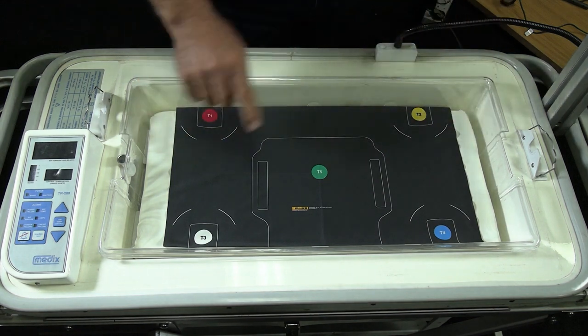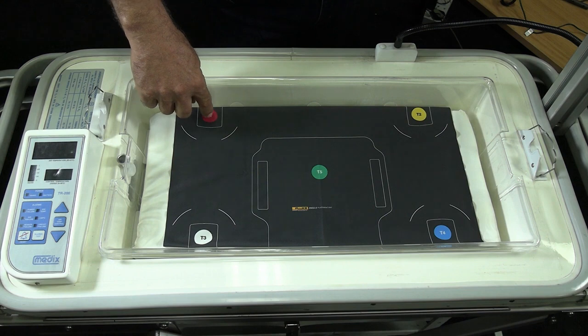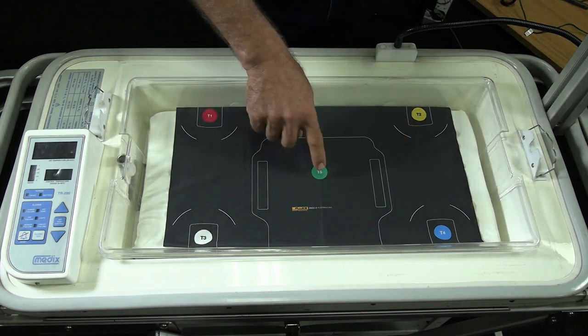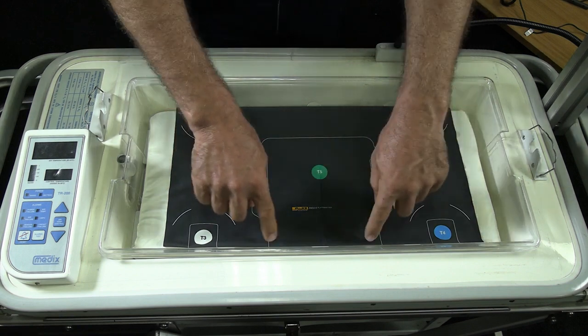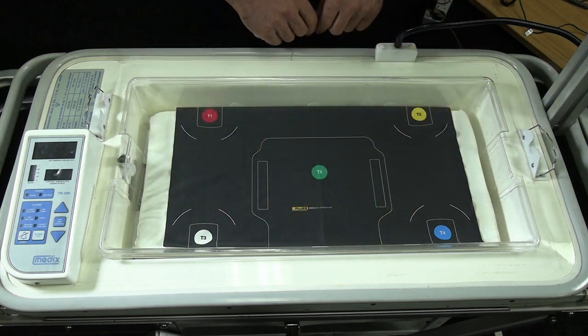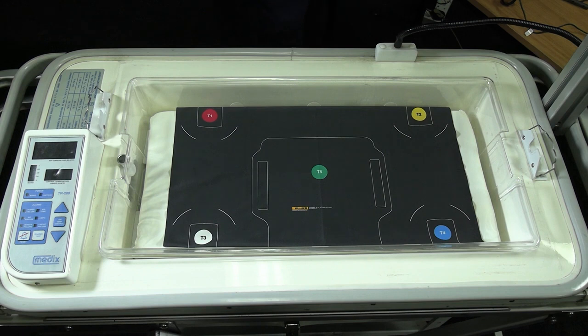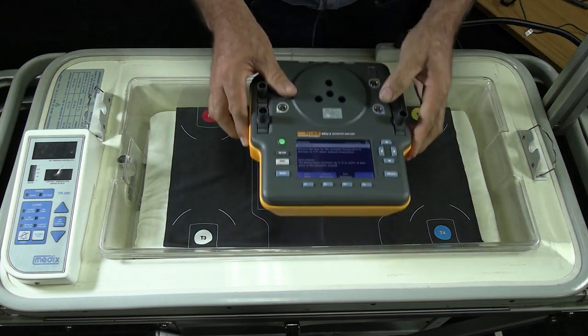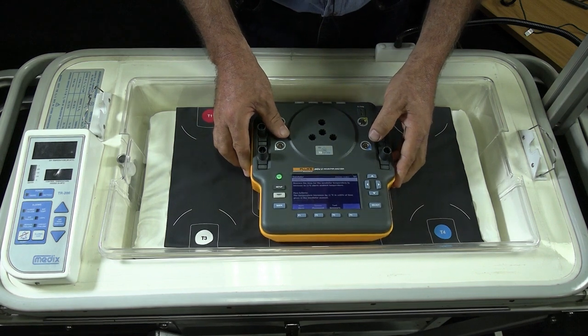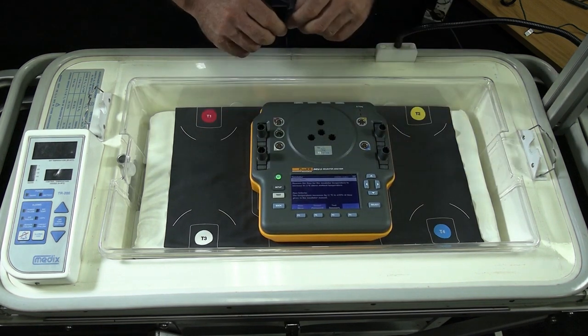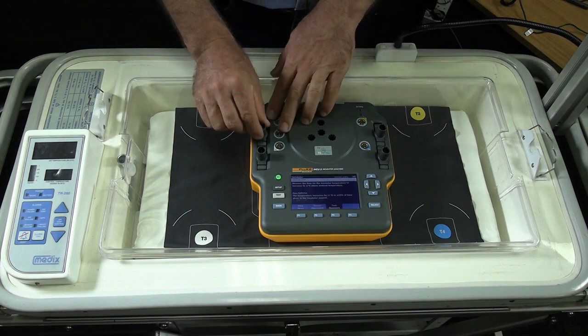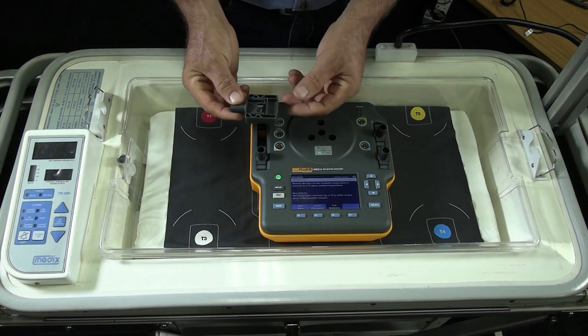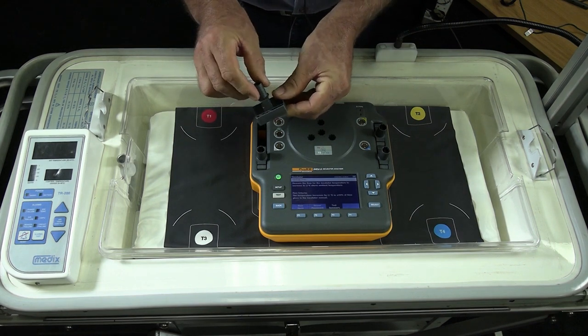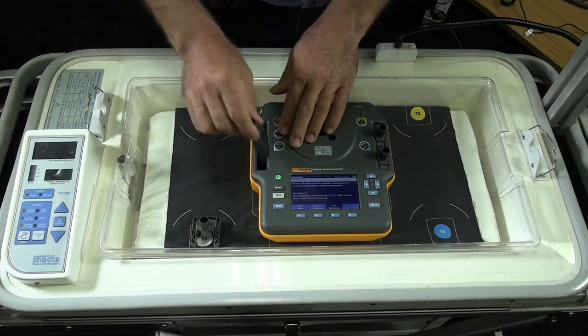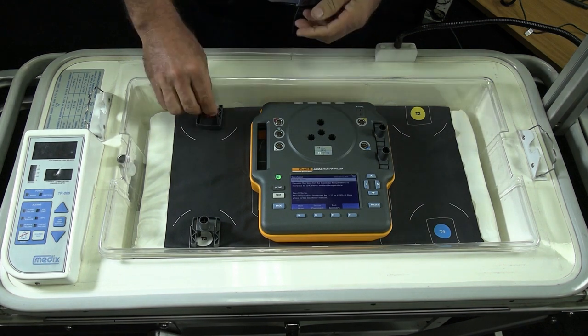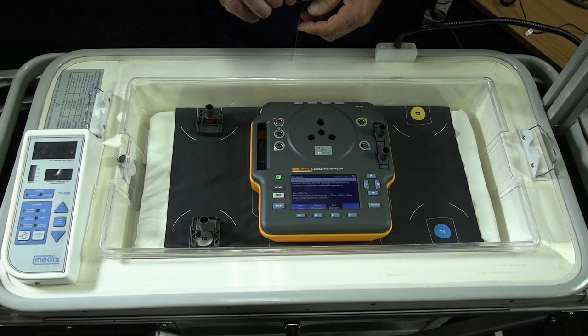Okay. And then also they are marked for the different temperature sensors, T1, 2, 3, 4, and T5. And then also the placement of our unit that needs to come in the incubator. So firstly, what we're going to do now is we're first going to place our unit as shown on the mat. Then you'll see on the unit we have these little pillars that can come out. Then we flip over and we use them for placement of the different sensors. They just keep them in position for us.